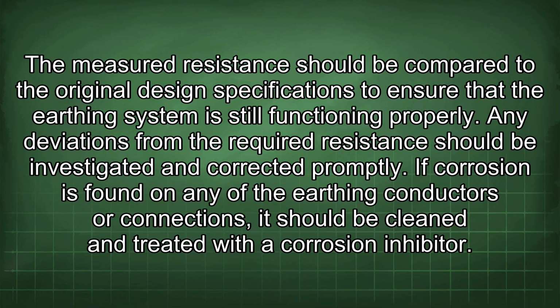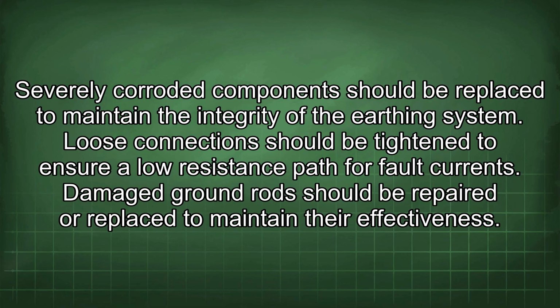If corrosion is found on any of the earthing conductors or connections, it should be cleaned and treated with a corrosion inhibitor. Severely corroded components should be replaced to maintain the integrity of the earthing system. Loose connections should be tightened to ensure a low resistance path for fault currents. Damaged ground rods should be repaired or replaced to maintain their effectiveness.